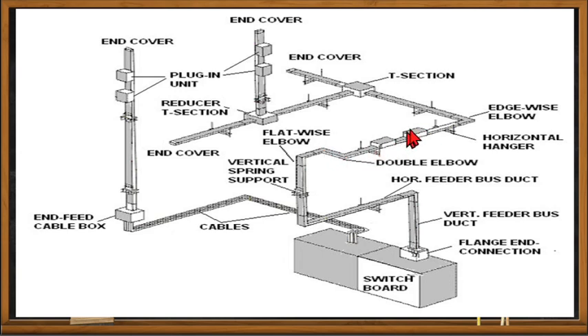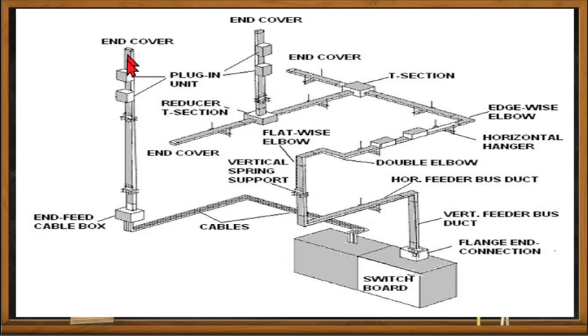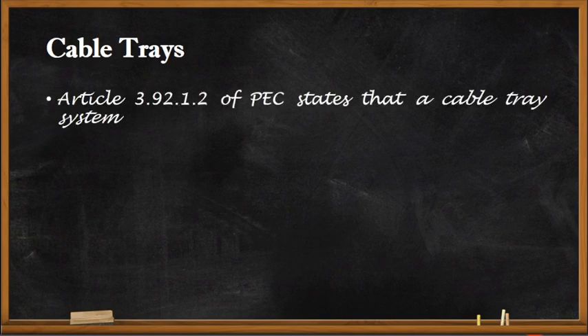We also have a double elbow for changing the run direction, a box sometimes used to reduce or enlarge the feeder bus duct, a horizontal hanger support, a T-section allowing two separate directions, and a plug-in circuit breaker box where you install the enclosed circuit breaker for your floor distribution panel.